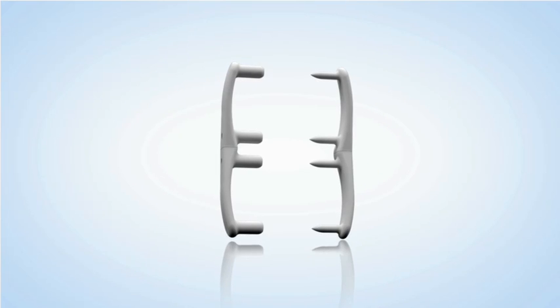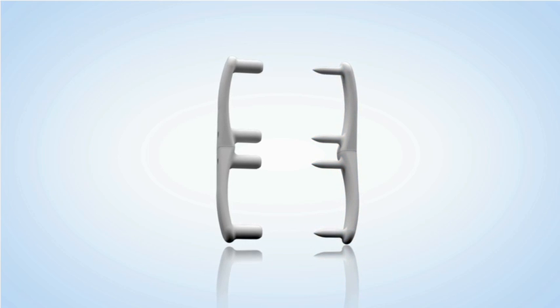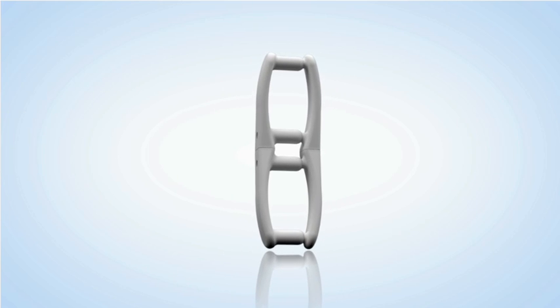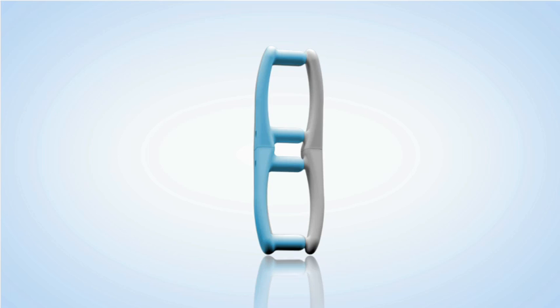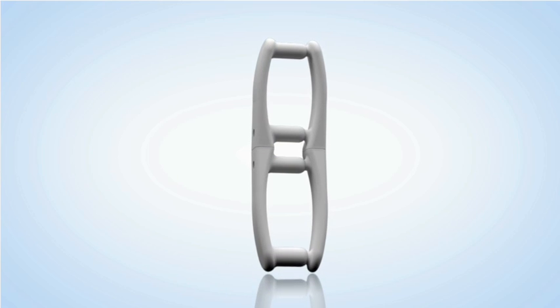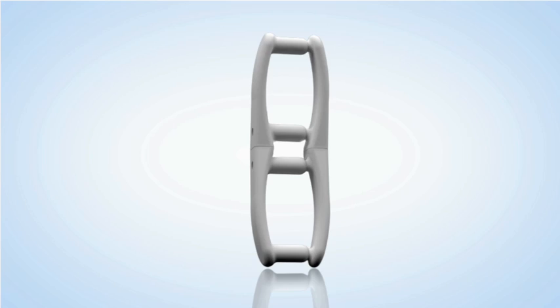As can be seen here, the device is made from two halves. The half on the right side in this illustration has spikes that are designed to easily pierce through the intervertebral ligament that runs between successive spinous processes. The other half on the left has a U-shaped receptacle for receiving the spike and locking into it. The mechanism can be further adjusted at each level to be individually customized and provide the correct amount of distraction and decompression.